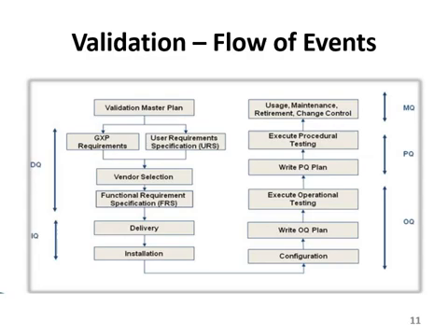Validation, flow of events. This is a nice picture, and if you go into detail of this flow of events, you can have a very clear idea of how the validation goes through the whole process, right? So the first thing is design qualification, DQ. You can see at the very left of the diagram, DQ is written, and at the top, validation master plan. So you have prepared a master plan for the process of validation, and then you are going to go through 2 steps.